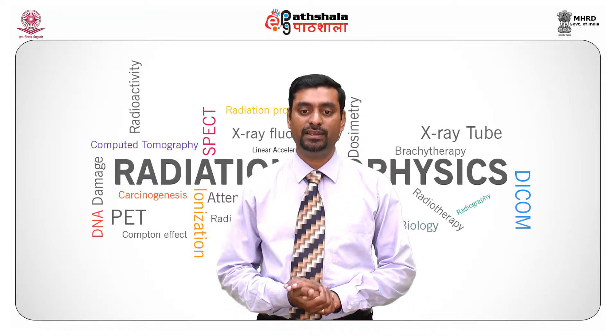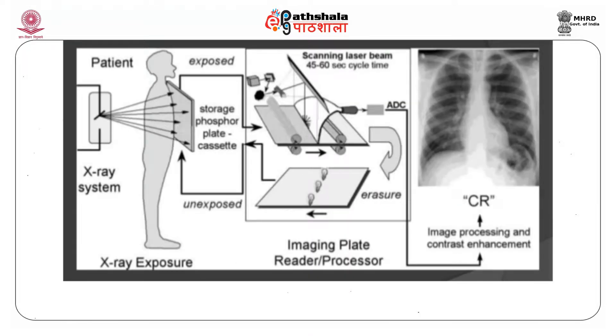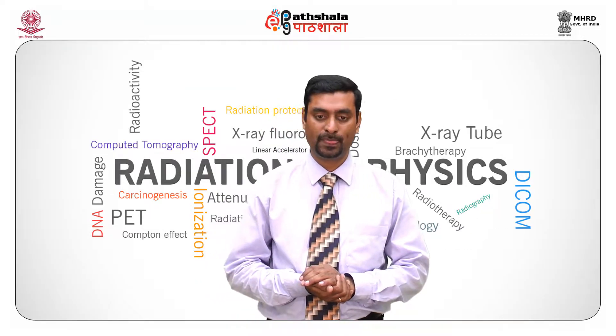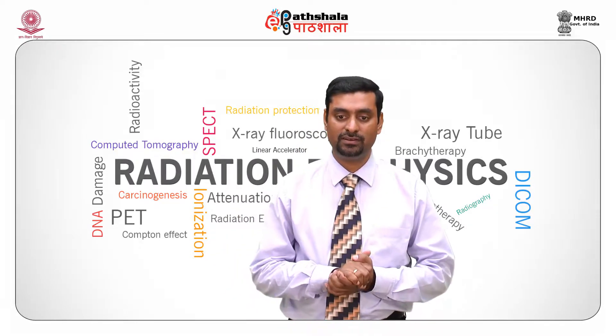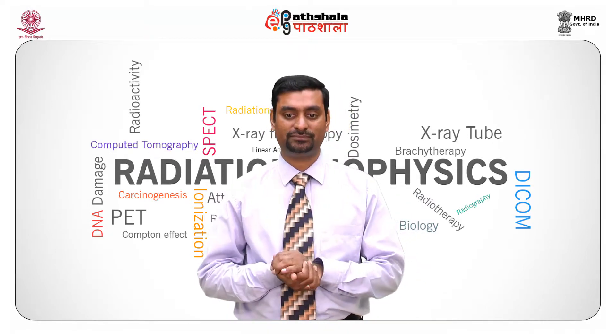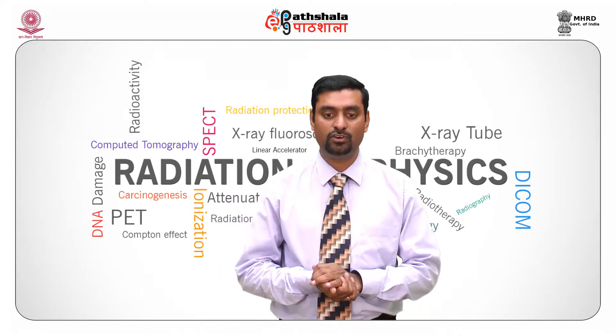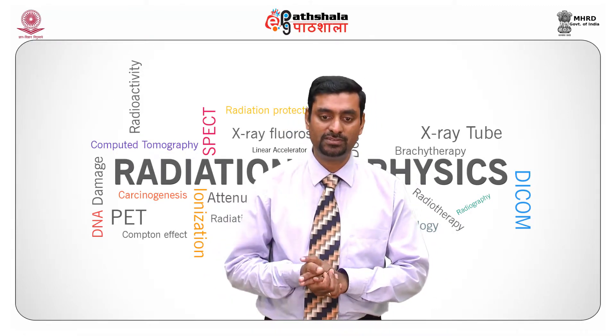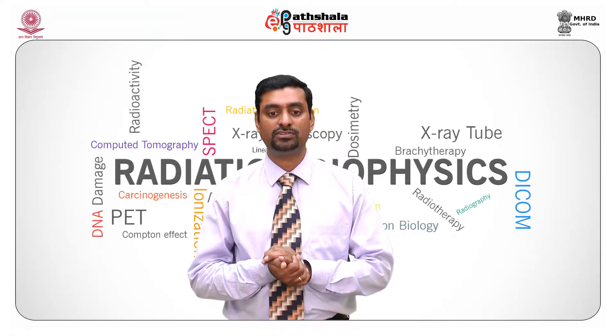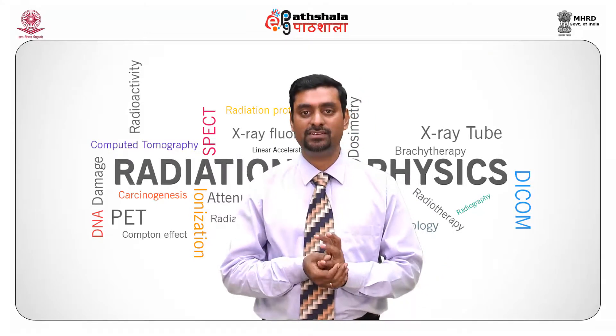Next we move on to the digital radiography system. In a digital radiography system there are flat panel detectors with indirect conversion — including charge-coupled device (CCD) and amorphous silicon technology — and direct conversion using amorphous selenium technology. The general principle of the CCD indirect conversion system is: x-ray photons from an x-ray machine fall onto a scintillation material such as cesium iodide or gadolinium oxysulfide, which converts x-rays into light. This light is passed through optics and in some cases demagnified before falling onto a CCD camera, which converts light into an electrical image.